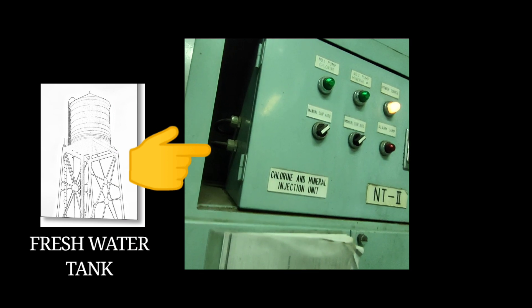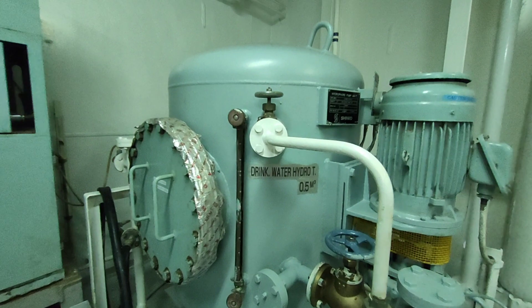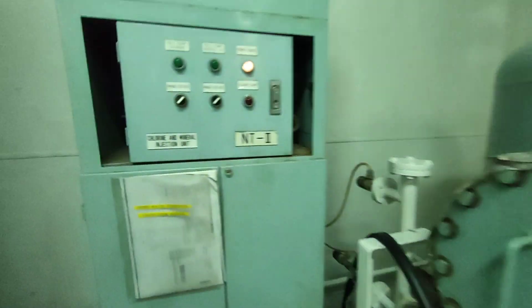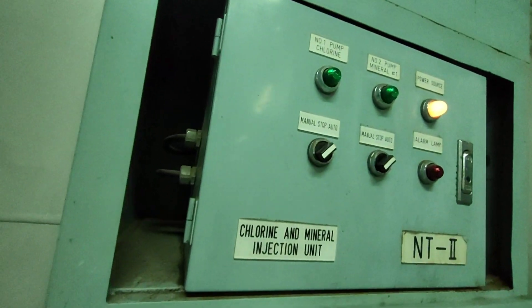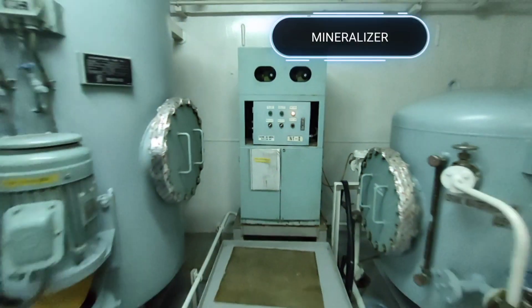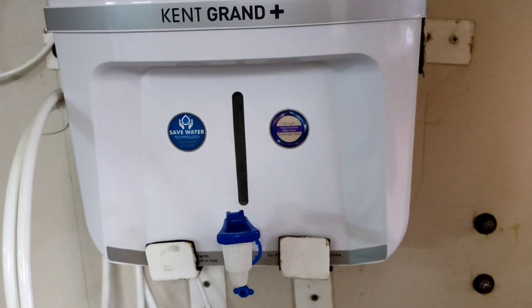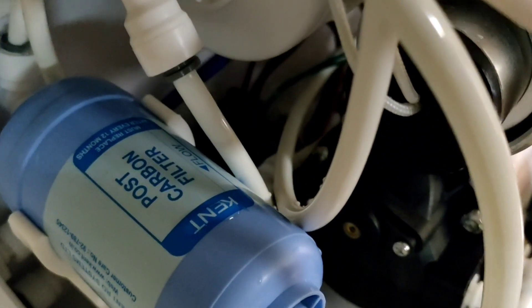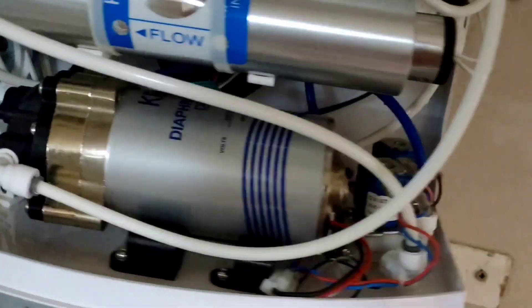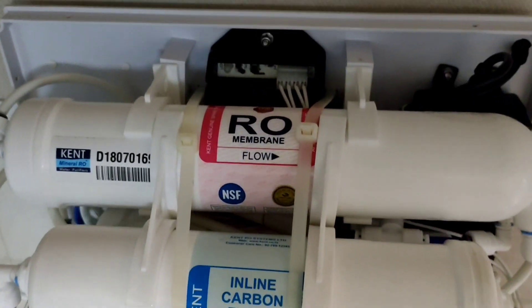However, drinking water will pass through a mineralizer unit, where minerals, chlorine, and inhibitors are injected. In some designs, the drinking water system is fitted with additional filters and UV lights to disinfect. In our case, it goes through one compact system unit comprising multiple stages such as UV light, sediment filter, carbon filter, and RO membrane — also known as reverse osmosis.